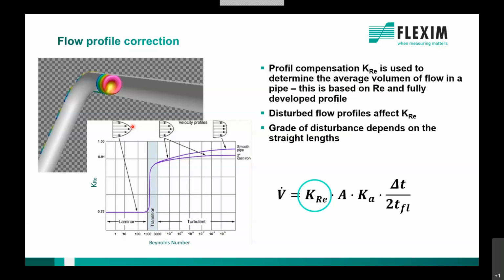And the question always is in the field, what is basically enough straight length to have an undisturbed flow profile, and what is the disturbance actually? When does it take place? That's really difficult to define in the field, and that shouldn't be the question when someone installs a flow meter, because those people should select the best spot on the pipe, definitely with the best straight length they can have, which is achievable on site. But it's quite difficult to find a spot which provides an undisturbed flow profile. And here our automatic flow disturbance correction comes into the game, which compensates those effects.